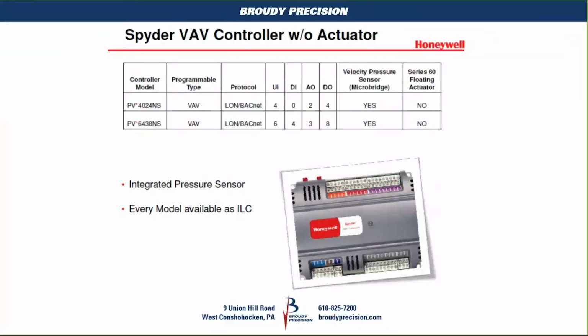Now, some of the retrofit jobs that we go on, it's not acceptable. That's too much. It's too big. We can't fit that direct coupled actuator on top of the shaft for the damper. So you may put the controller in, maybe mount it to the ductwork or in a separate location, and wire the floating Series 60 actuator back to this controller. And you'll notice now that you have a PV4024 and a 6438 because the dedicated digital outputs are now back on board, since the actuator is not included. And again, it has the integrated pressure sensor and is also available in the ILC as well.